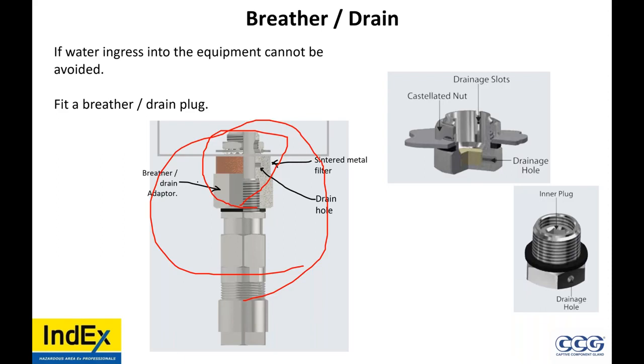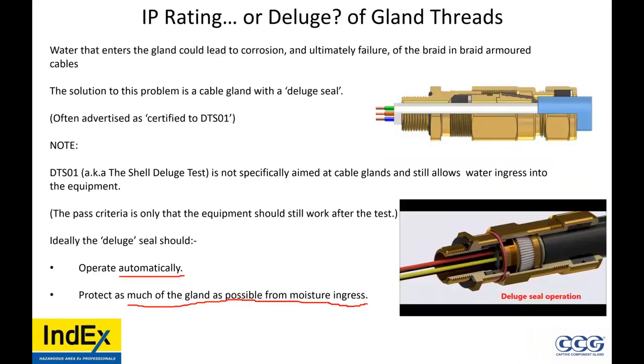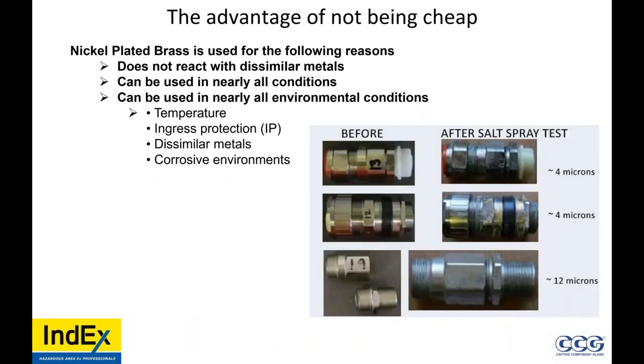Correct. Finally, one little comment on the plating thickness of the nickel plating. Until a few years ago, you were limited to 8 microns of plating on a cable gland. That restriction was lifted, and the general consensus is that less than 10 microns, what you have is decorative. 10 microns plus, what you have is protective. So it's very, very important to specify at least 10 microns of nickel plating, and preferably a marine grade nickel plating, because not all nickel plating is the same.